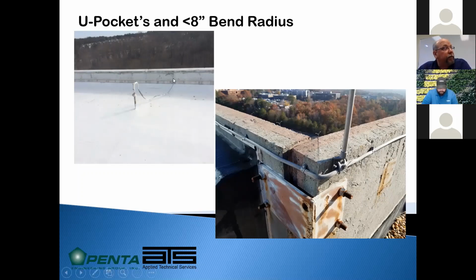This is a U-pocket. So we're coming down off of a parapet loop over to a down conductor, but then we're rising at too great of a slope. And then we also have a bad bend here. It's a good waterproofing detail, but it really is not doing a lot. And the energy of a strike is going to try to arc off it around here and try to find a different pathway. In this particular photo, there's not many other pathways near, so it might still function as designed.